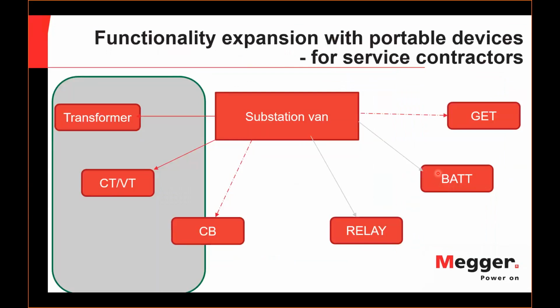We were talking the last 2 days about transformer assessment, but especially service companies often go to a substation and see not only transformers, but also CT, so current transformers, voltage transformers, circuit breakers. Sometimes the same people are also testing battery discharge or protection relay systems. As you can see on that very schematic slide, the existing test van is already covering a big share of the substation. And if you take a few portable devices, you can easily cover the rest of your daily needs. You can see this solution as a full-scale substation test van.